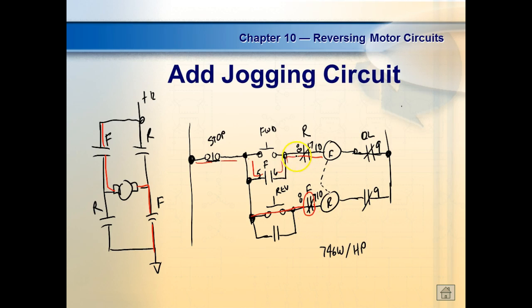No, what you're going to do is say, well, I need it 8 to 7, and you're going to wire it to 8 and 7 on the forward instead of 8 and 7 on the what? On the reverse. So that 8 and 7 is not on this one, it's going to be on this one, right? You understand? And of course, it's obvious when you do that, because you press the forward button, it energizes. As soon as it energizes, it drops out. As soon as it drops out, it energizes. So anybody press the start button, it goes like that. What does that mean? You got them wired to the wrong relay. Somebody in this class is going to do it, sure.